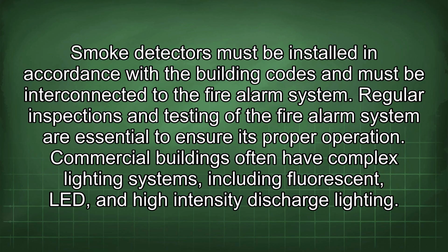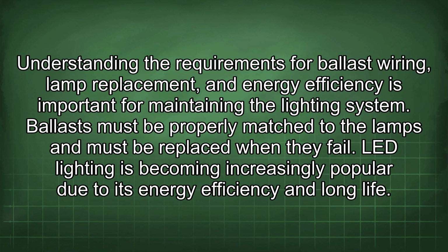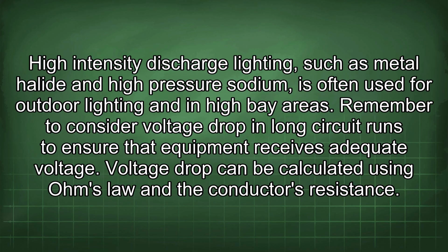Commercial buildings often have complex lighting systems, including fluorescent, LED, and high-intensity discharge lighting. Understanding the requirements for ballast wiring, lamp replacement, and energy efficiency is important for maintaining the lighting system. Ballast must be properly matched to the lamps and must be replaced when they fail. LED lighting is becoming increasingly popular due to its energy efficiency and long life. High-intensity discharge lighting, such as metal halide and high-pressure sodium, is often used for outdoor lighting and in high bay areas. Remember to consider voltage drop in long circuit runs to ensure that equipment receives adequate voltage.